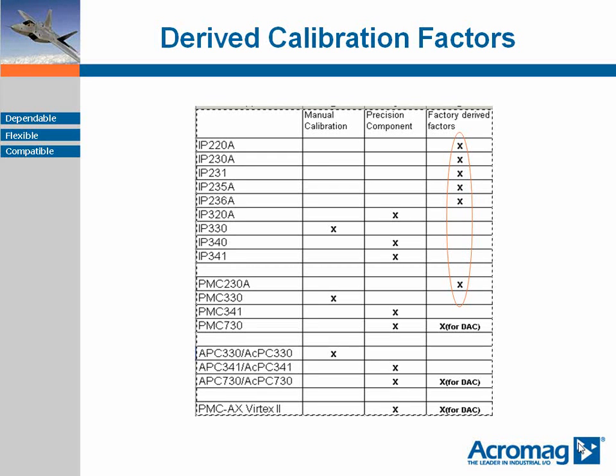In the case of analog output boards, the board is programmed to output a series of expected values during the final test process. The recorded output is used to compute a set of correction factors which are written into each board. These factors can be overwritten by the customer with some effort, but it is not recommended.